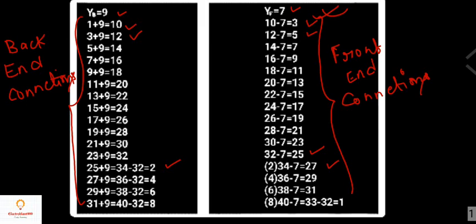Since 25 plus 9 equals 34, but there are only 32 conductors, we subtract 32: 34 minus 32 equals 2, so the 25th conductor is connected to the 2nd conductor. Then 27 plus 9 equals 36, and 36 minus 32 equals 4, so the 27th conductor at the back end is connected to the 4th conductor.